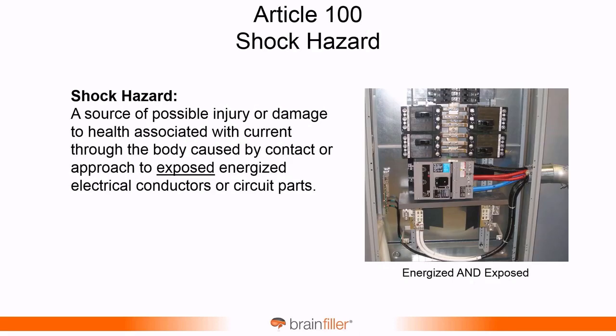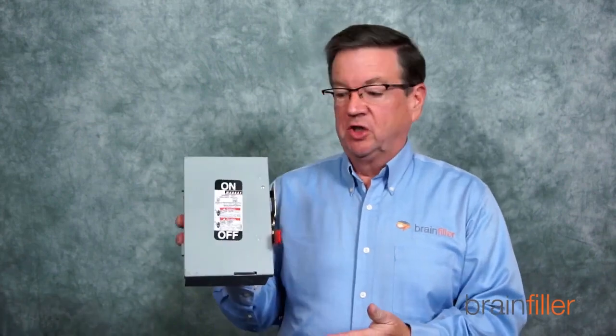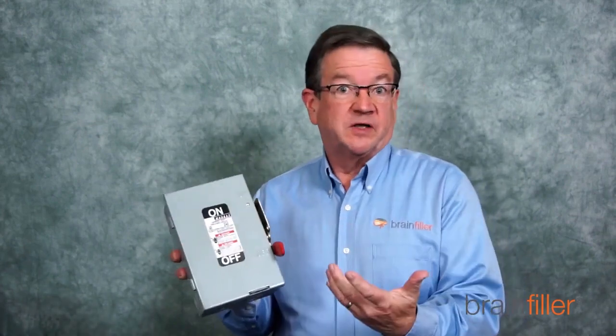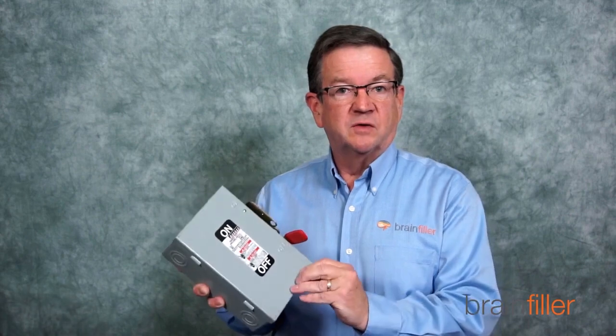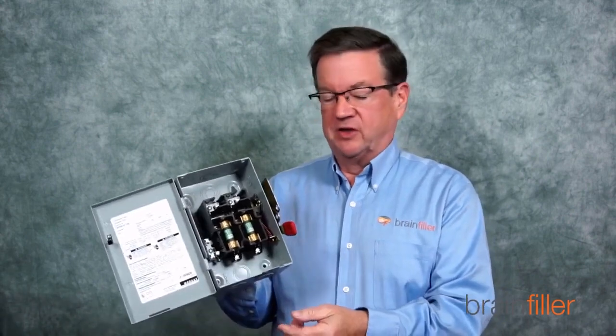Another change to a definition, the shock hazard. Now, this seems simple enough. It's a source for possible injury and damage to health, but the word exposed was added because it did say caused by contact or approach to energized electrical conductors. And so there's a clarification, exposed energized conductors. For example, if you have a switch, there's energized conductors in here, but they're not exposed. So it's not a shock hazard. Whereas if you open it up, you may be thinking, Jim, the switch is off.